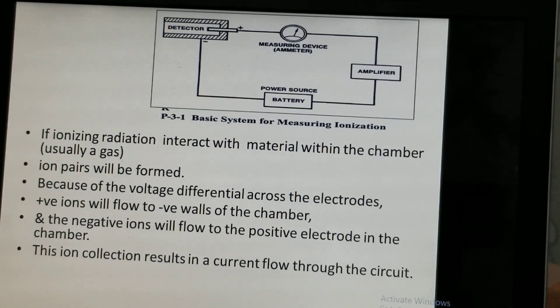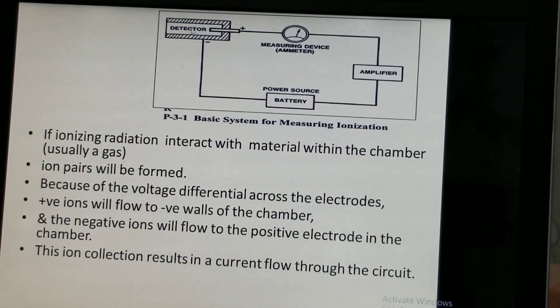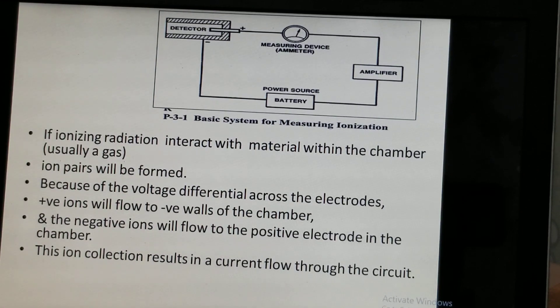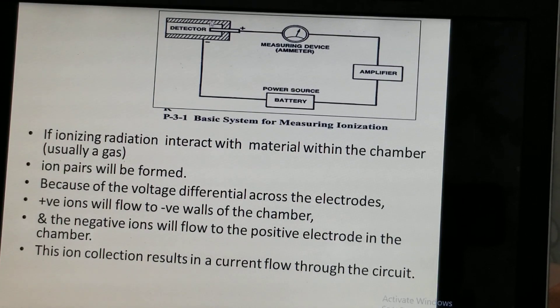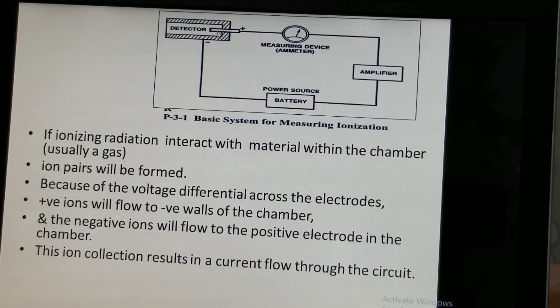When ionizing radiation interacts with the material in the chamber — which is usually filled with gas — ion pairs are formed. Due to the voltage differential across the electrodes, positive ions flow towards the negative electrodes (the chamber walls), and negative ions flow towards the positive electrode (the central wire). This ion collection results in a current flow through the circuit.